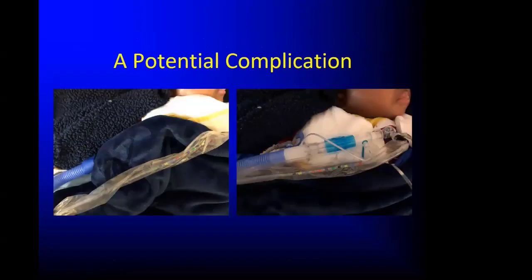One of the things you have to be careful of when you use a passive circuit, remember, that's just a hole, and if that hole gets blocked up, then what you've done is created dead space. And so a patient can become hypercapnic even though you've not changed any of your ventilator settings, just because that expiratory valve is obstructed. So make sure it's always visible when you're using a passive circuit.